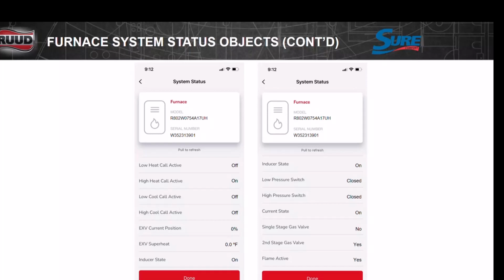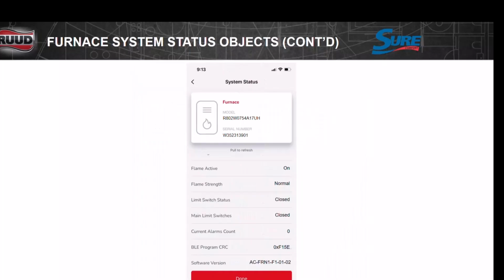Flame sensor tells you what kind of flame, that it's active. In other words, we've got fire. And whether our pressure switches are closing, our limit switches. Here's our limit switches. Our flame sensor strength. The flame sensor is an electronic communicated device now. It's no longer check your microamps. It comes back as like a digital signal back to the board to tell you what strength you're running, whether it's normal or low. So you can't check it the old-fashioned way anymore. But the app's going to tell you if it's the flame sensor or not. It sees your limit switches, and it gives you current alarm count. It means how many times it's gone out on alarm. And, of course, the software version again.